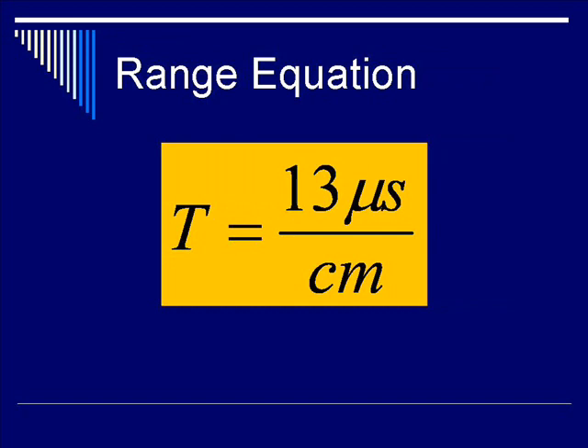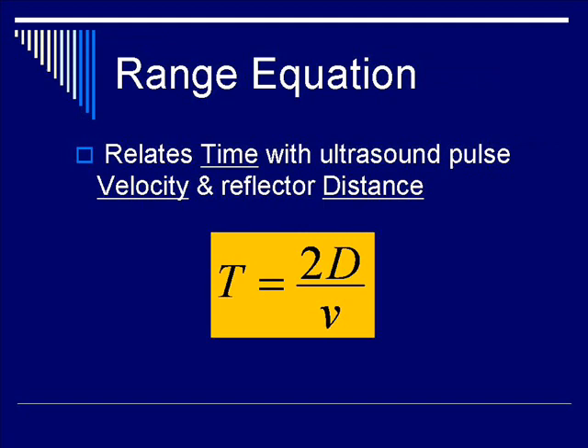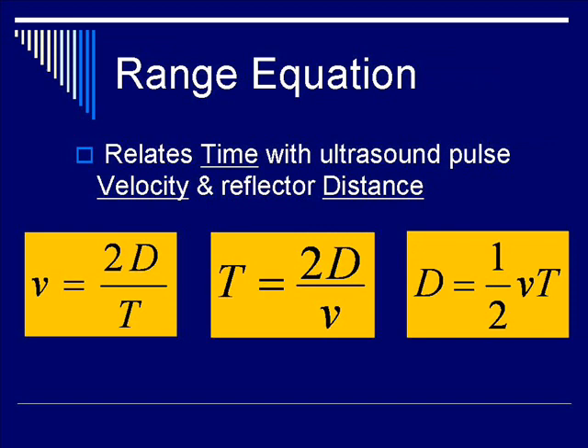Another equation often used is T equals 13 microseconds per centimeter depth. This is a shorthand because it also relates time with velocity and distance. There are many variations of this equation. You have T equals 2D over V. You can also find velocity as V equals 2D over T, or calculate distance D equals VT over 2 if you know the velocity of the ultrasound pulse and the round trip time.